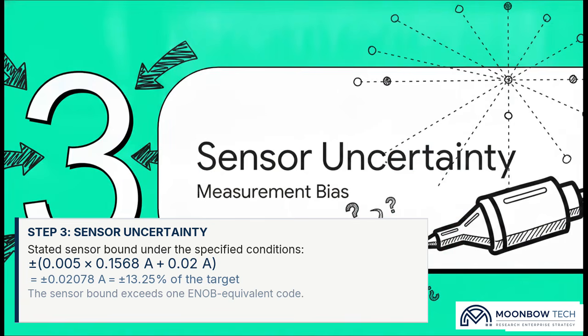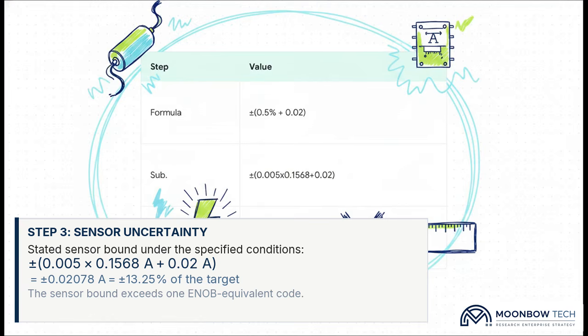And that brings us perfectly to step 3, sensor uncertainty. We have an external transducer making the physical measurement, right? Let's look at its stated uncertainty bounds. The formula provided by the manufacturer is plus or minus 0.5% of the reading plus a fixed 0.02 amps.